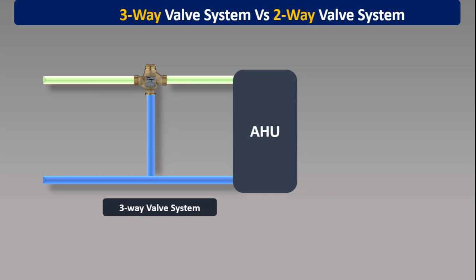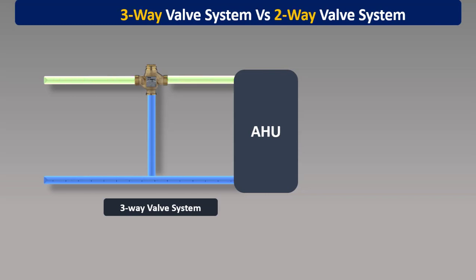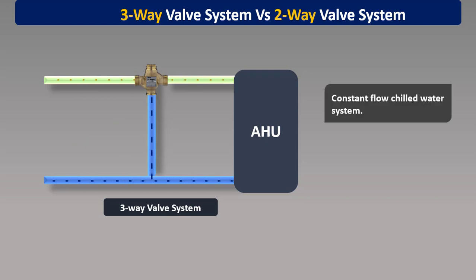Before discussion about the chilled water system, let's have a brief discussion about three-way and two-way valve systems. In the three-way valve system, three-way valves are used — these valves have three ports. A mixing three-way valve is used with an AHU to control the chilled water flow through the cooling coil. Chilled water flow is modulated to achieve the desired set point of the AHU supply air. When cooling load is reduced, the valve will be partially closed, resulting in flow through the bypass line from the supply chilled water line to the return chilled water line. The three-way valve system is a constant flow system where chilled water flow through the system is constant at all times.